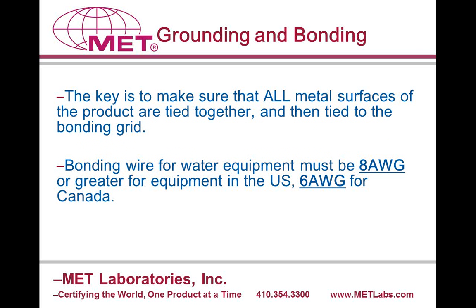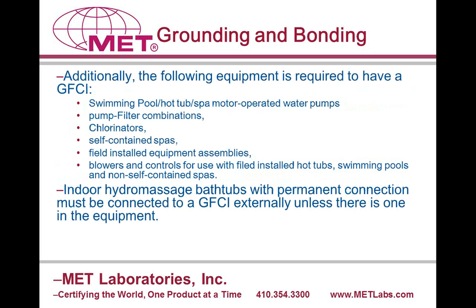So the grounding, in essence, is what the customer does when the unit is plugged or wired in to make a connection to the plug or earth ground. But the bonding is what you design to make sure that every piece of metal is interconnected. Notice that the gauge of the wire is huge. The gauge for U.S. equipment is 8 AWG. The gauge for Canada is 6 gauge. That's how important bonding is to electrical products around water.